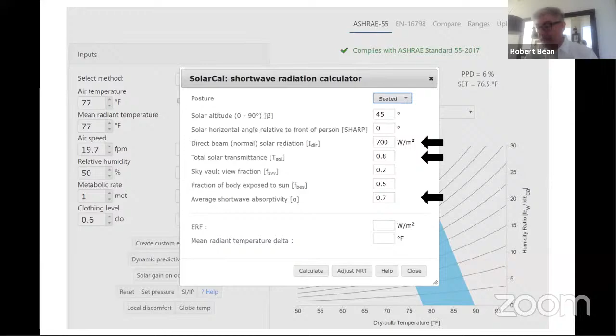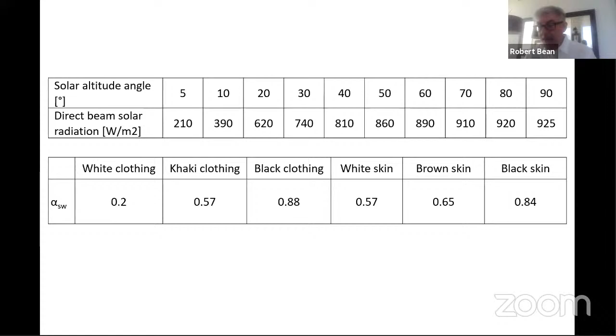When we put in these values, we see an effective radiant field, or how much it changes the mean radiant temperature perception. ASHRAE Standard 55 provides guidance if you don't know the angle or altitude for your area, and it provides the absorptivity depending on the clothing and skin, whether light or darker colored. When we put that into the tool, it does the offset.